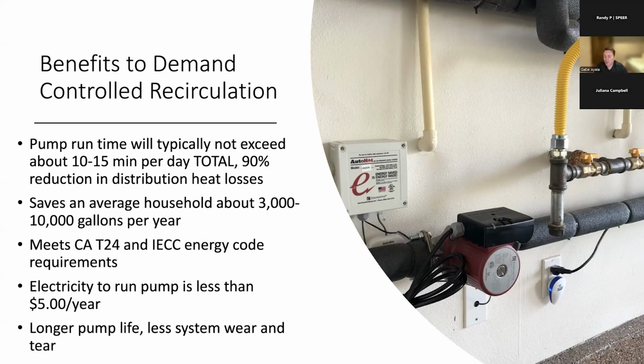Another thing to note is that if you look at tankless water heater warranties, basically for all tankless water heaters across the spectrum, whether it's Rinnai, Navien, Noritz, Rheem, take your pick, they all have a warranty that says it's either 10 years or 12,000 hours on the heat exchangers. So any time that the tankless is seeing flow, it's tracking that runtime, and it's just chipping away at the number of hours that you have on that warranty. So if you have a pump that's running for hours and hours out of the day, that's depleting that warranty faster. If you have a tankless water heater, the main strategy should be to control the pump as much as possible so that you extend the full useful life of that equipment.